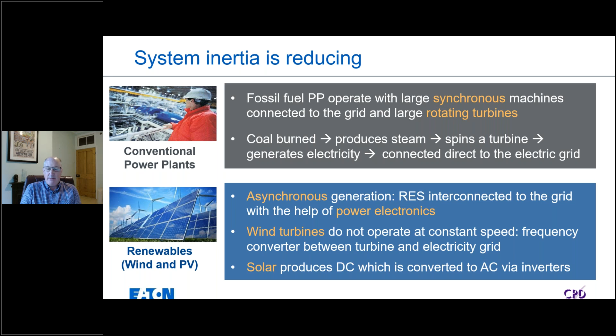So I've mentioned inertia a number of times there, but what is it and why does it matter? If we go back to our GCSE physics, according to Newton's first law, inertia is the resistance of an object to a change in its motion. So in this example, the motion that we're talking about is that rotating mass of the large synchronous generators. And that's storing energy through that rotating mass, which is spinning at the same frequency as the grid. And when we refer to power system inertia, that is simply the sum of the multiple large generators connected onto the system. So there's a huge amount of inertia carried there. That effectively acts as a sort of shock absorber, and that slows down the rate of change of frequency when, for example, a generator trips out or a large load is switched on.